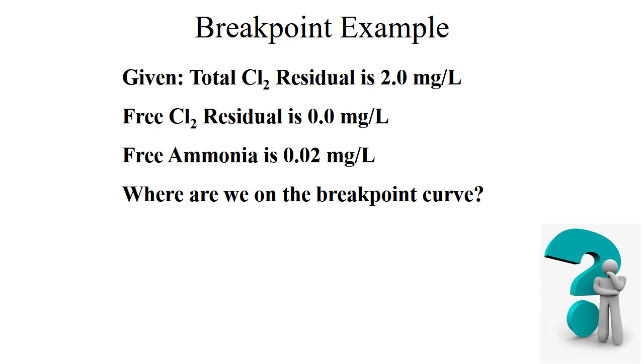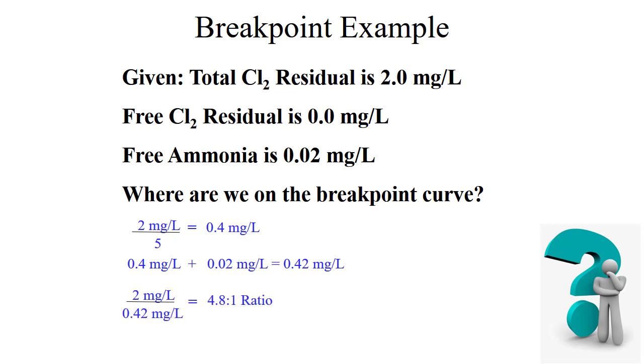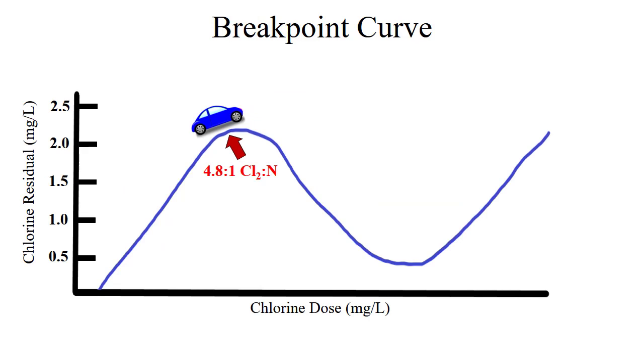In this example, the total chlorine residual is 2 mg/L, the free chlorine residual is 0, and the free ammonia is 0.02 mg/L. Since we have free ammonia and no free chlorine, we know we are to the left of the 5-to-1 ratio. As in the previous problem, the first step is to determine the ammonia dose at a 5-to-1 ratio: we divide 2 mg/L by 5 and get 0.4 mg/L. Then we add the free ammonia concentration of 0.02 to get a total ammonia feed rate of 0.42 mg/L. Next, we divide the chlorine residual of 2 mg/L by the ammonia feed rate of 0.42 mg/L to get a chlorine-to-ammonia-as-nitrogen ratio of 4.8-to-1. A 4.8-to-1 ratio is a good ratio for a plant to operate at since it minimizes the amount of free ammonia entering the distribution system.